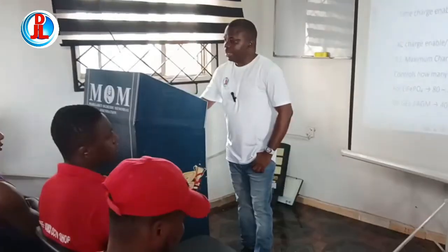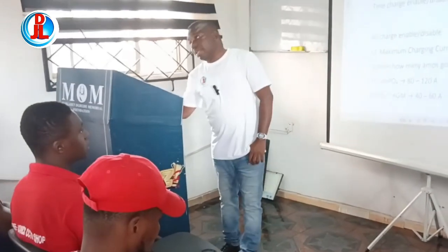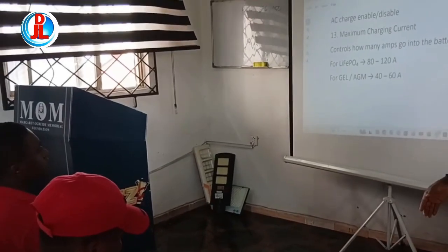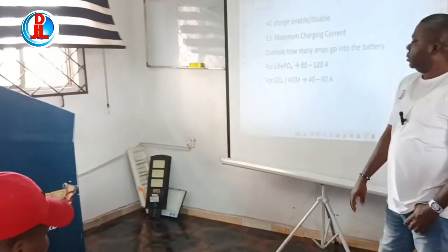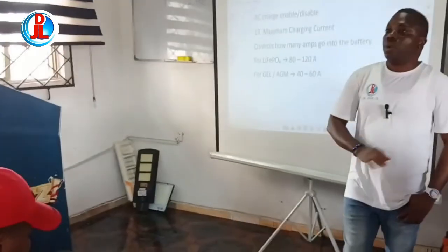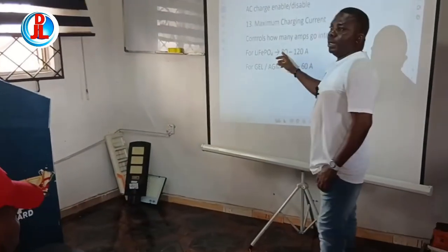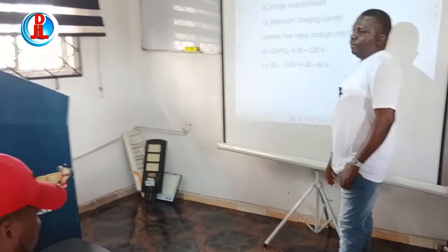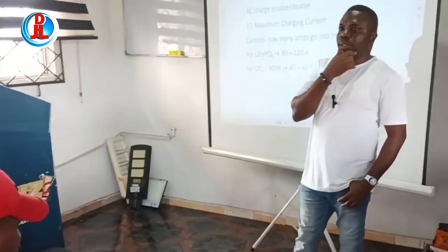Time charge, enable or disable. AC charge, enable or disable. Look at your AC charging, enable it. Don't disable it so that you can actually be charging. Maximum charging current. Now look at this. Very, very important. For my lithium battery, the charging current is between 80 to 120. For my tubular battery, between 40 to 60 amps. Did you understand? So that means like times 2. I told you that charging current is 10% of the rated amps for tubular, while for lithium it is 20% of the rated amps.